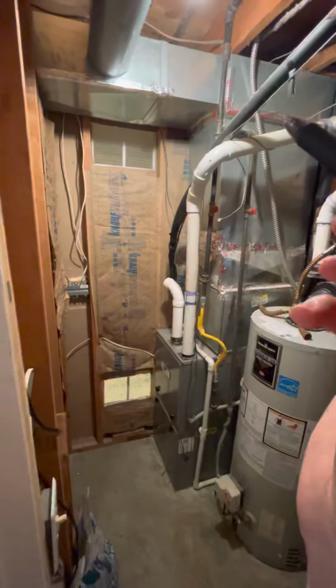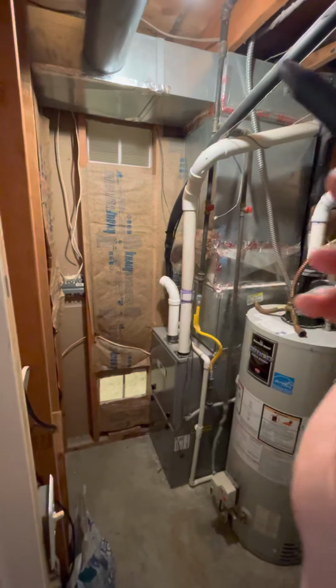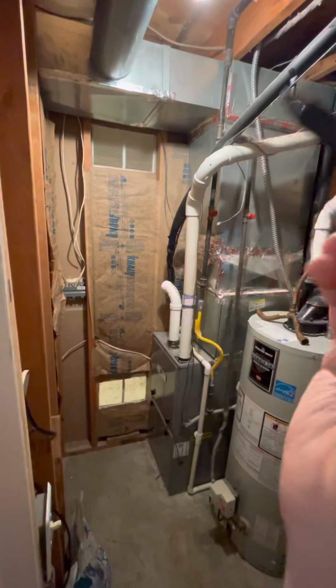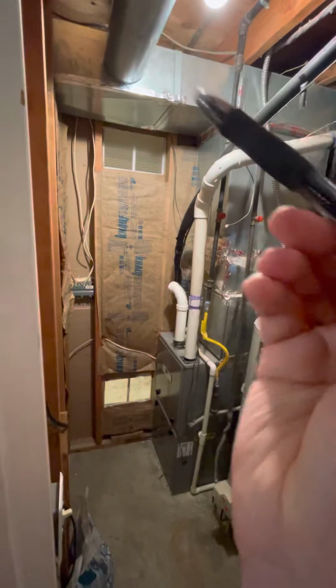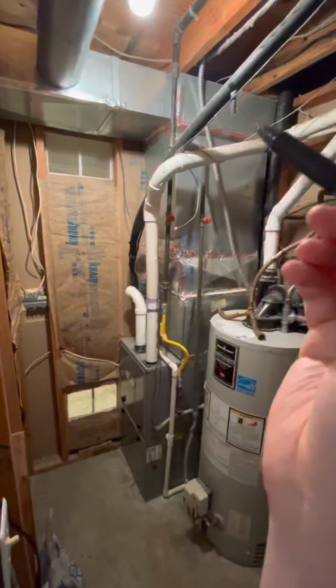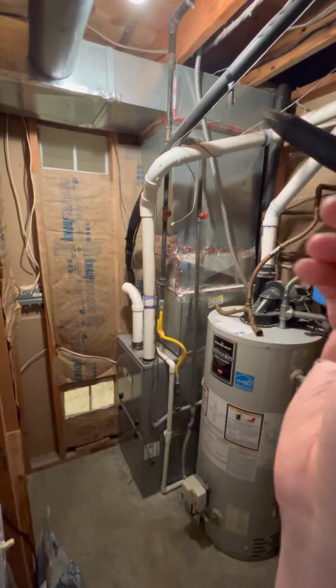And the main reason I'm saying that is because there's a lot of airflow that needs to go over here and down that way, which we might even need to add turning vanes inside this to direct that airflow, so there's no pushback or any backflow coming off of this duct right here. I'll show you guys where that's all running to. So it runs directly over, and then we have this entire supply line that feeds this entire basement. And I'm assuming they have a couple more runs off of that because their floor joists are running this way. This is going to be the existing cold air return and the only cold air return. It's a 16 by 25 and it has a 16 by 25 by 1 filter in there.